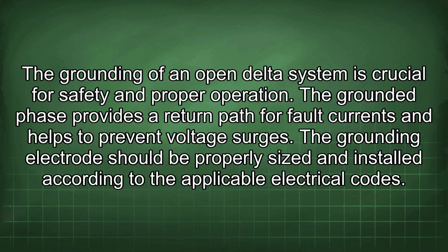The grounding of an open delta system is crucial for safety and proper operation. The grounded phase provides a return path for fault currents and helps to prevent voltage surges. The grounding electrode should be properly sized and installed according to the applicable electrical codes.